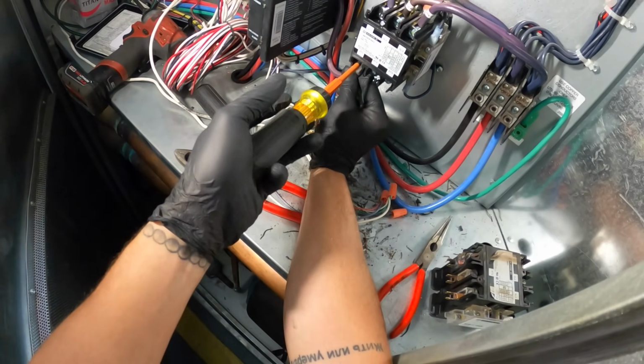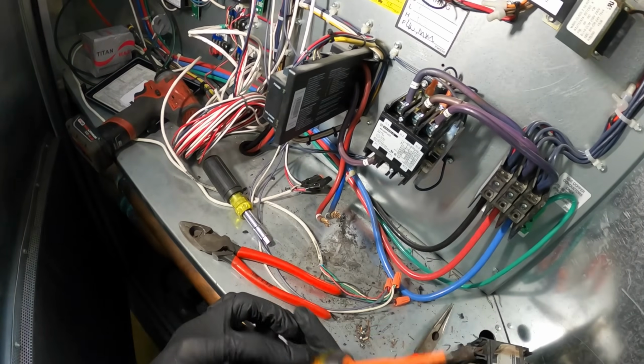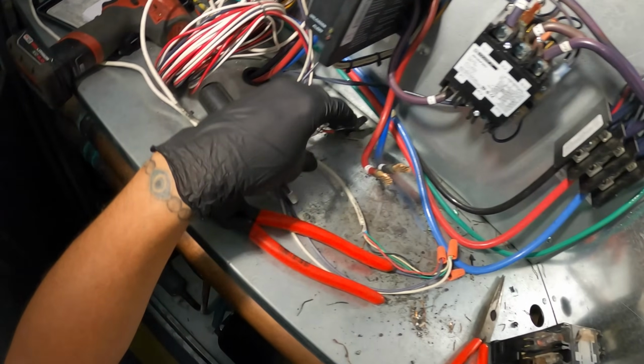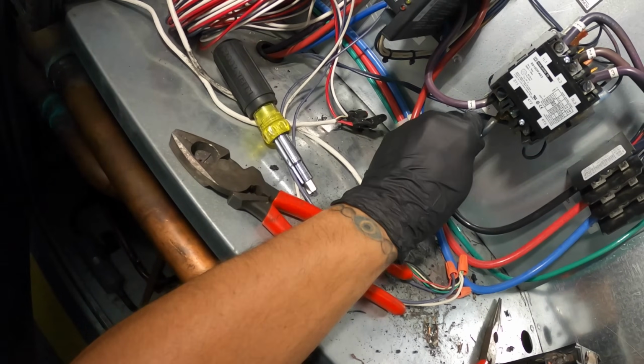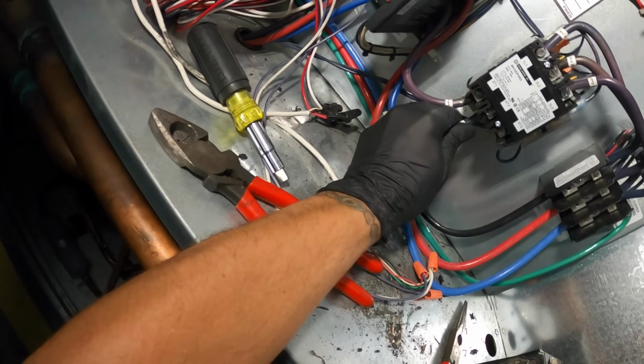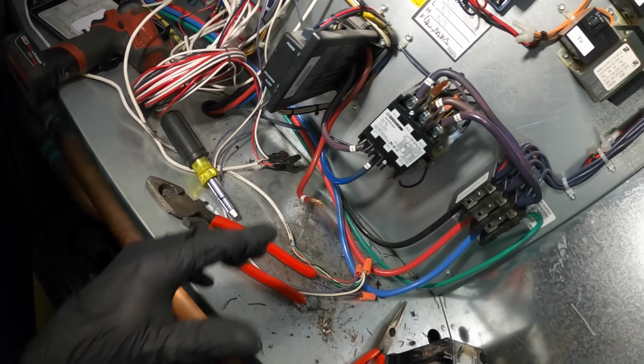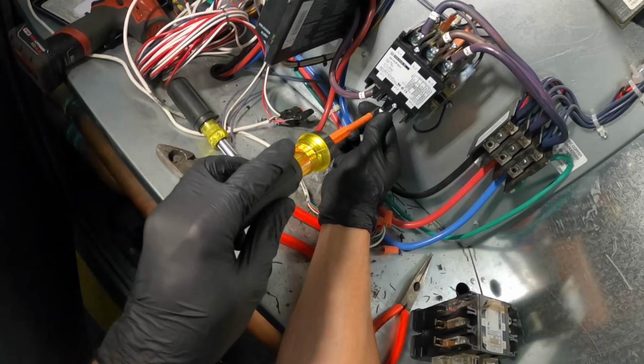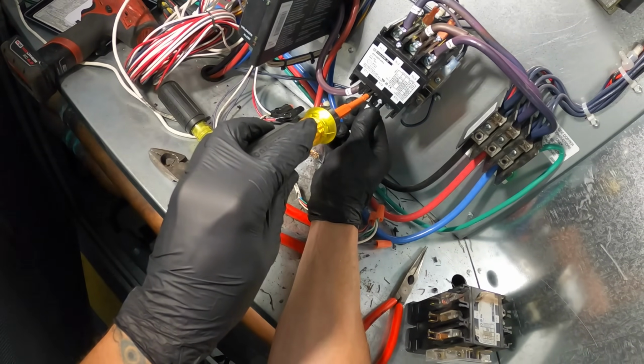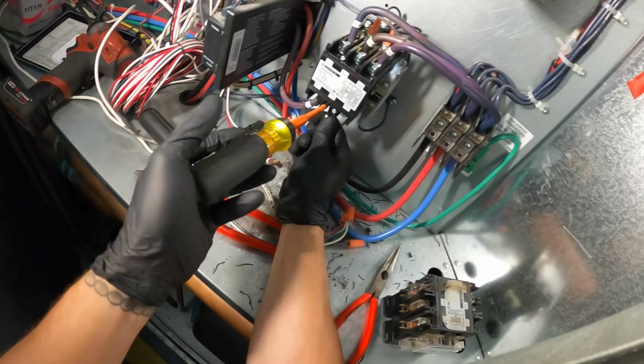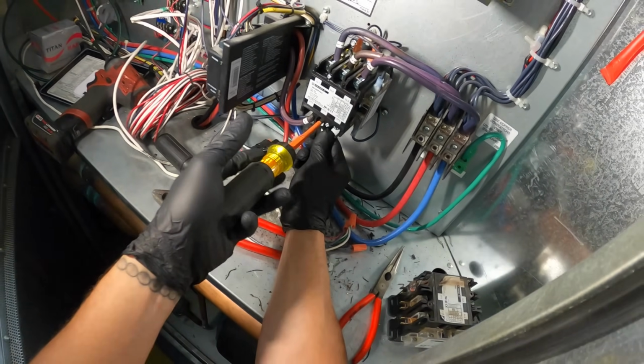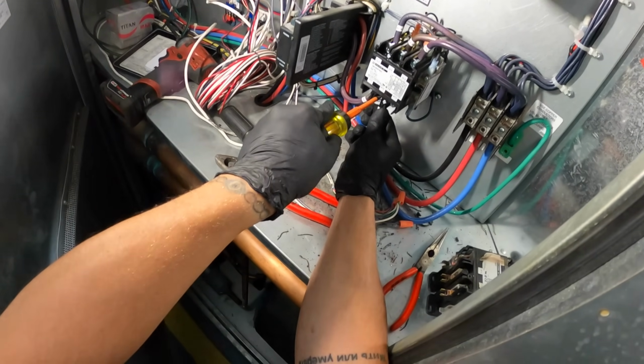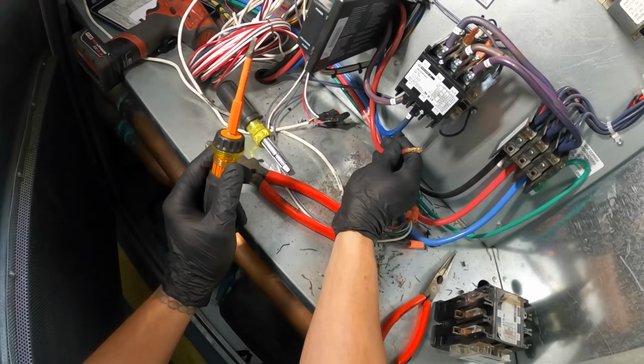Thing is, sure, we fixed the burnt wire and everything, and we cleared that code because we know now that the unit runs, you're gonna be okay. Thing is, why did this thing burn out? What failed? I've seen this thing had a couple of loose connections that can cause amps to go up, and that could definitely fry things.